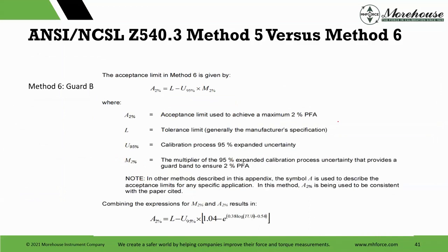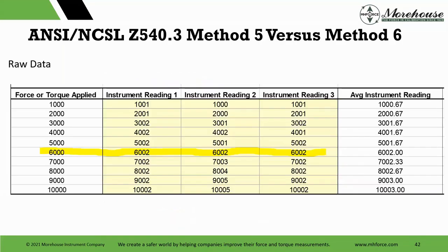I'm not aware of many places where that is actually discussed, but it's built into the sheet. You can see it. So method 6, which some call the Dobbert method, uses this formula. It calculates an acceptance limit of 2%: the tolerance limit minus that 95% calibration process uncertainty, and then it uses this other multiplier, which provides a guard band to ensure 2% PFA. It basically tells you, are you in or out? And if you're within the calculated acceptance limit, the risk is less than 2%. It's a great method.